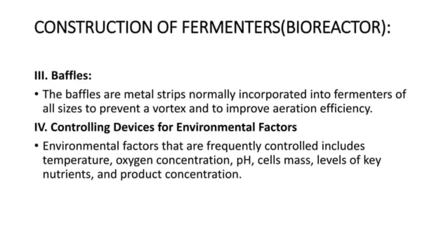Baffles. The baffles are metal strips normally incorporated into fermenters of all sizes to prevent the vortex and improve aeration efficiency. Controlling devices for environmental factors. Environmental factors that are frequently controlled include temperature, oxygen concentration, pH, cell mass, level of key nutrients and product concentration.